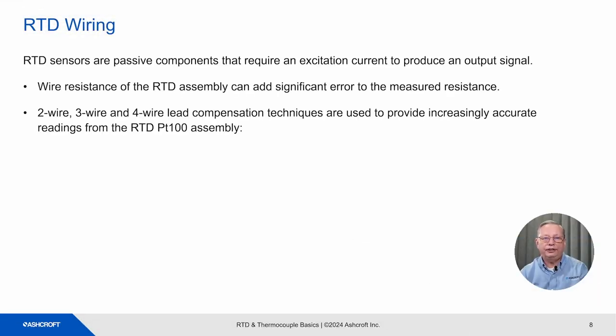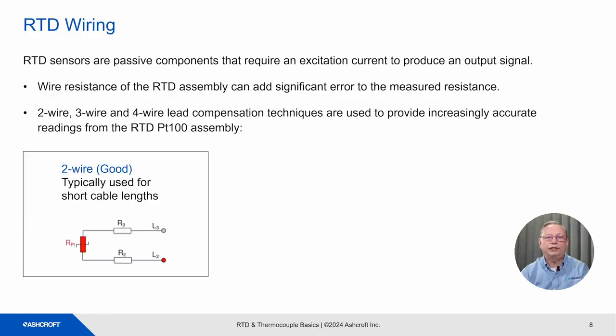RTD wiring. RTD sensors are passive components that require an excitation current to produce an output signal. The resistance of the wiring used can add significant errors. There are three wiring methods: 2-wire, 3-wire, and 4-wire. In the 2-wire method, the resistance of the lead wire is added to the RTD resistance, and this could possibly be a significant error. 2-wire is typically used with very short cable lengths to minimize potential error.